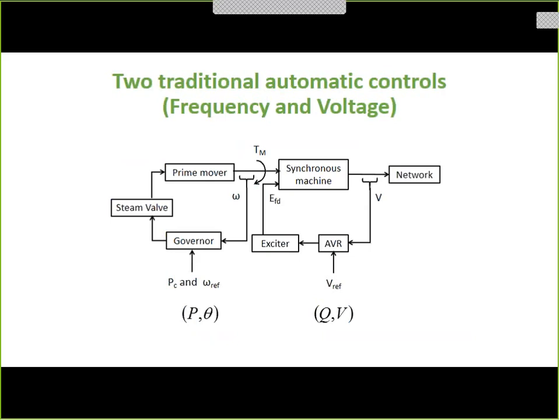I want to go through some modeling stuff. There are two traditional automatic controls. By automatic, I mean they're PI and they're automatic continuous, constantly controlling the grid. The two most important things, frequency and voltage. You got to have 60 hertz, otherwise you're in trouble. You got to have rated voltage, otherwise you're in trouble. So those are really only the two things that people care about. So I have shown here on the left part all the frequency related stuff. The prime mover is the turbine that turns the shaft of the generator. It has a governor built into it, and I'll show you what one looks like in a minute. There's a steam valve that opens and closes the steam. Or you can think of that as the gas pedal on your car, whatever you want to think of it as. But the point is, it's controlling real power, P, and the angles on the voltages. So it's called P theta.